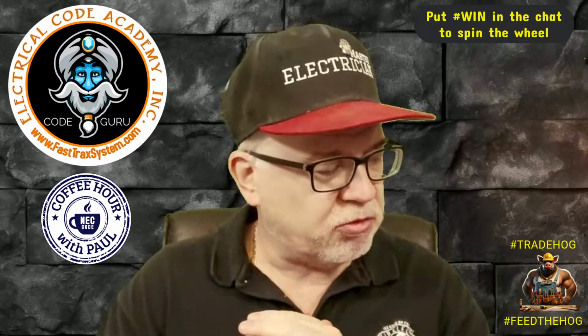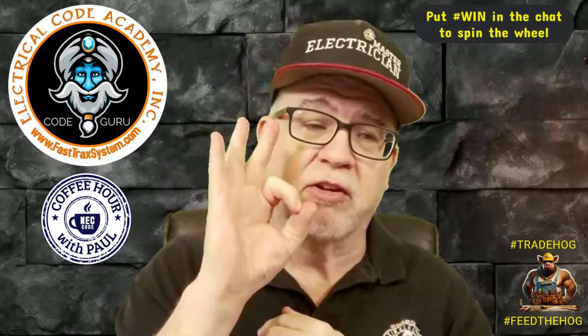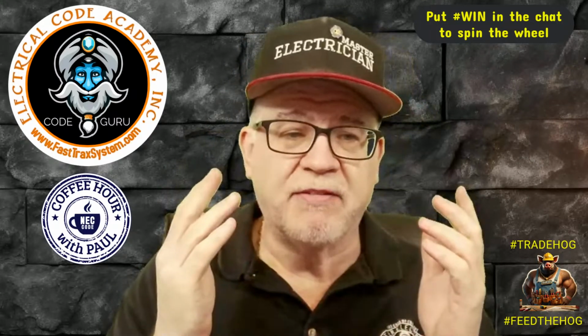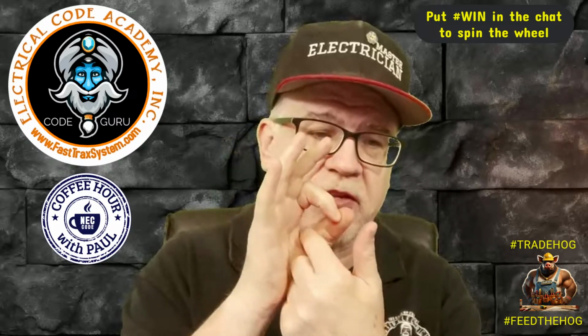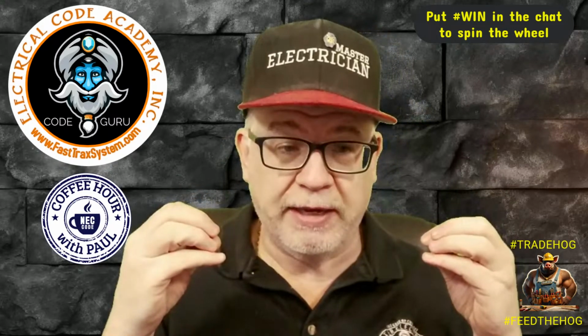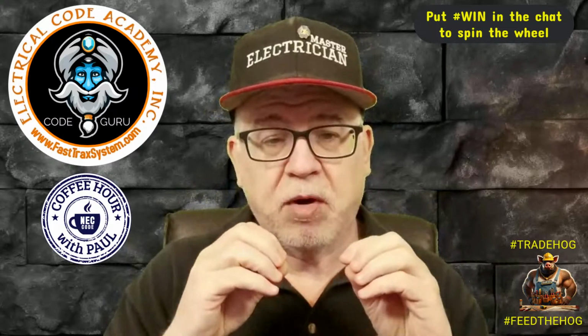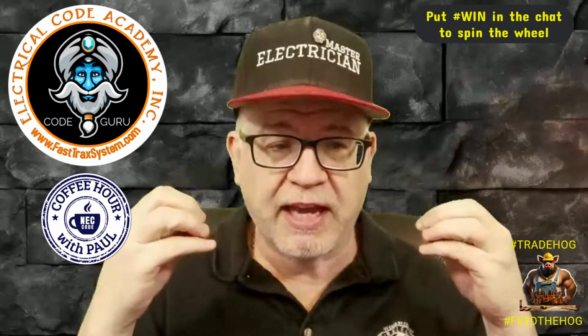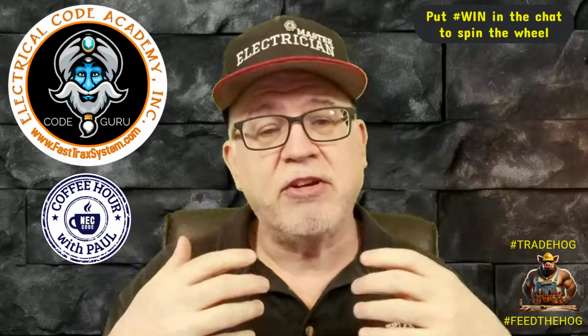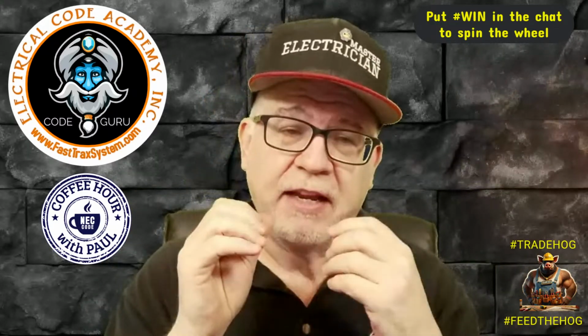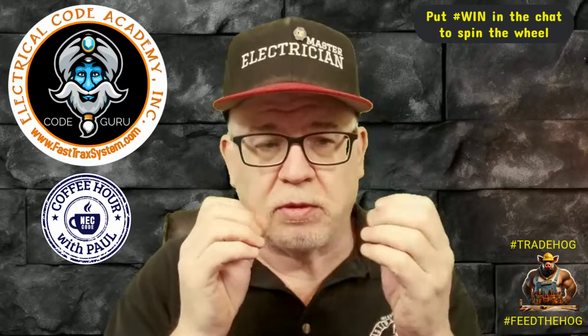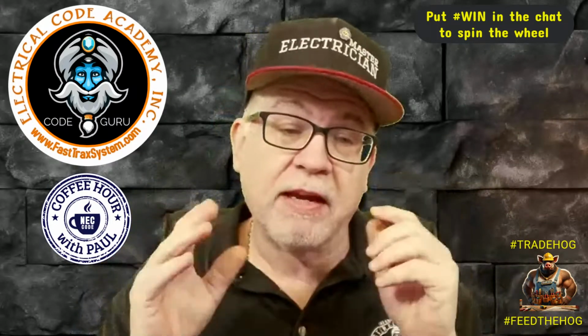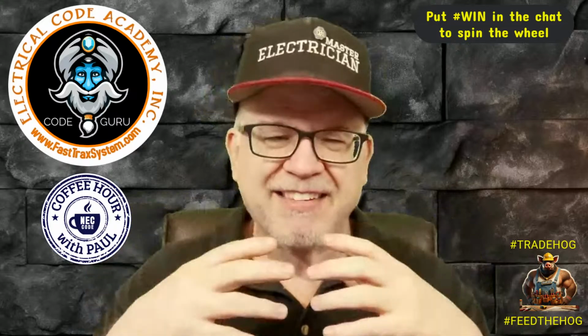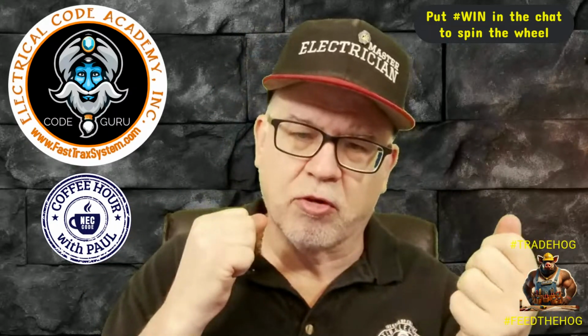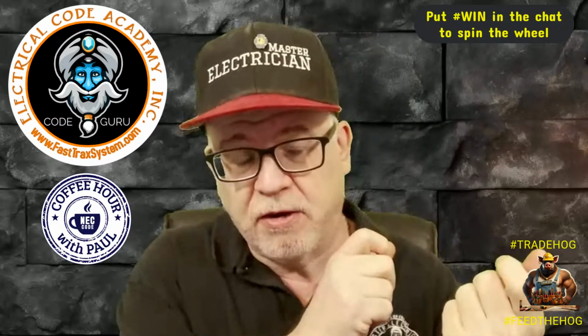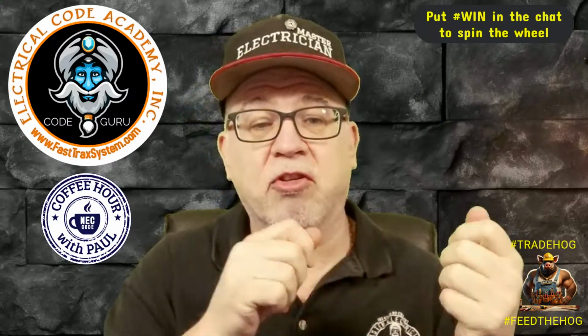So basically, the easiest way that I explain paralleling is the same as in a stranded conductor. You have a stranded conductor, let's say a 500 kcmil, right? You have like 37 strands or whatnot in there. Well, they're all acting as one, even though they're separate individual strands. When you connect them together at both ends in a single conductor, it acts as one conductor and you're getting a certain amount of ampacity out. But each individual strand is distributing the current equally, right? So when you think of that same concept and you have multiple sets, it's the same thing, right? You're connecting them at both ends so that those multiple conductors per set or per phase, A, let's say, are acting as one conductor.